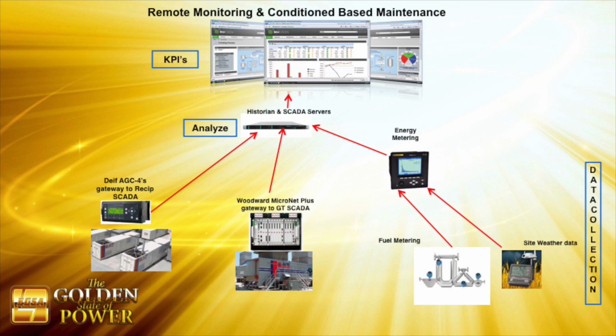But to do that, you need to know exactly what's coming in. So using mass flow meters, whether it be liquid or gas, using weather data, we need to know what the ambient site conditions are. Are we within our specifications for what we're guaranteeing to the customer? When we talk turbines, we're talking 15 degrees Celsius, so we cross-reference everything back to 15 degrees and show that we're compliant.